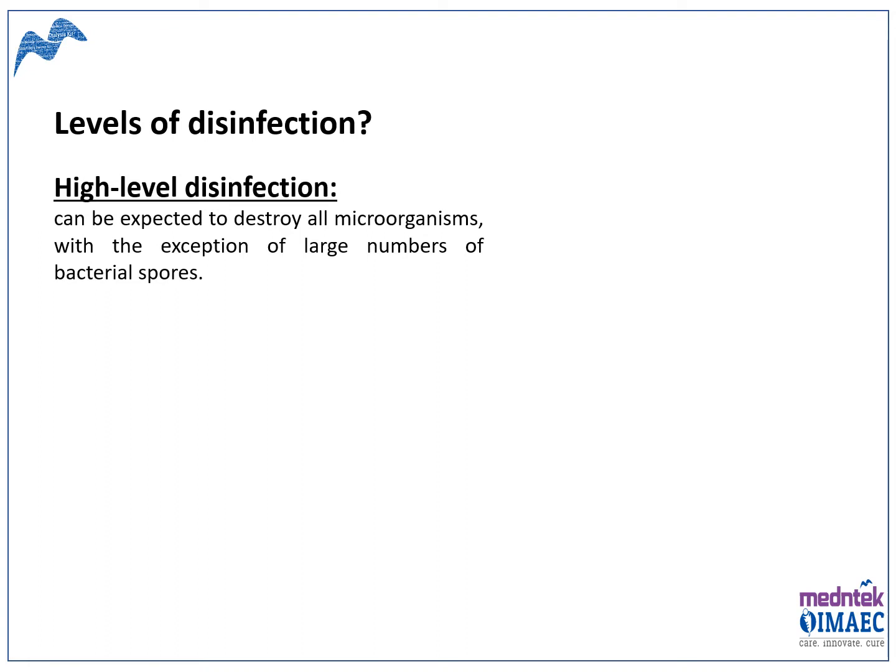And the best is the autoclave, because the autoclave uses 121 degrees Celsius and 15 lbs pressure, and that moist heat penetrates the bacterial spore. So the autoclave is a complete form of sterilization, but the high level disinfectant process is one step below sterilization, and that is known as sterilant.